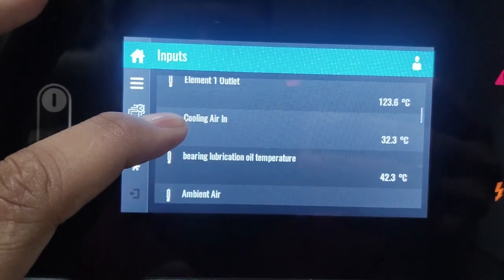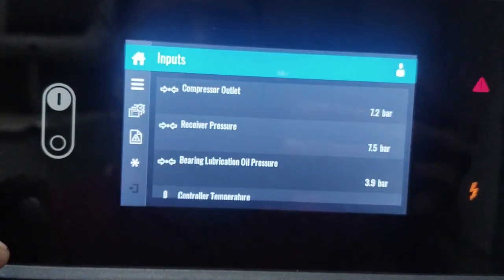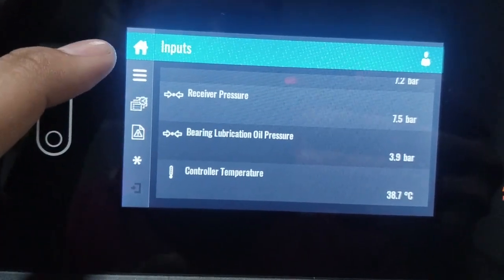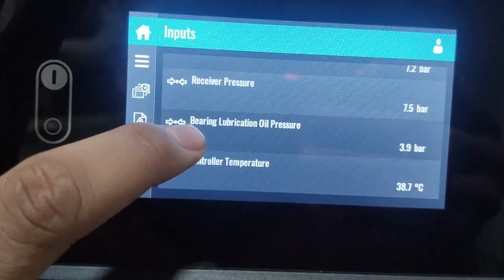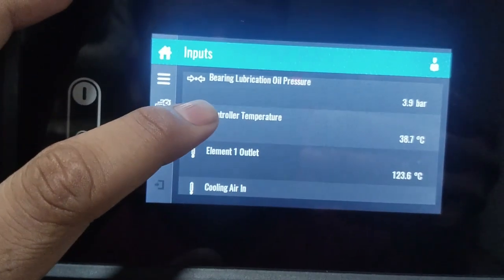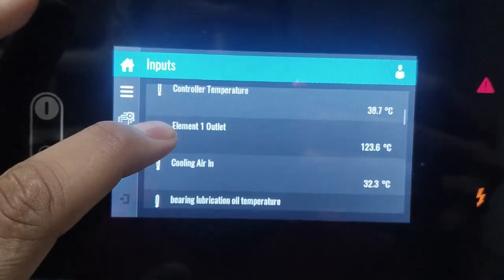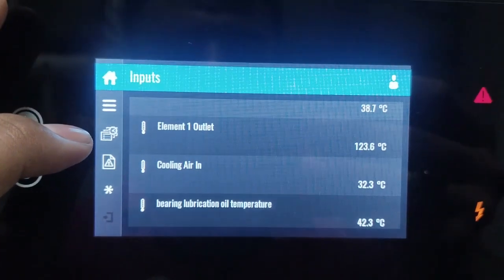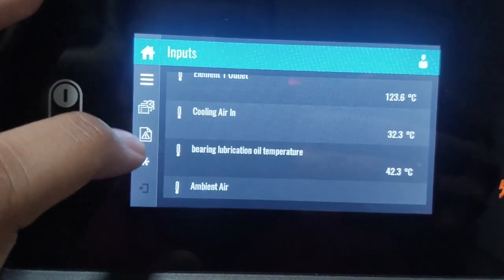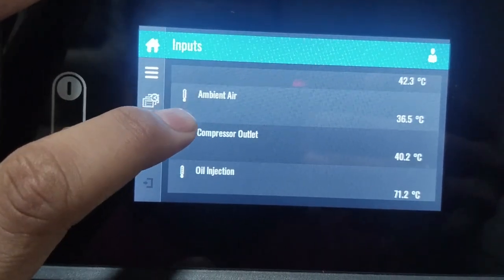Here you can see the compressor status is showing shutdown — the main reason is high temperature trip. Looking at the parameters during shutdown: compressor outlet pressure was 7.2 bar, receiver pressure was 7.5 bar, bearing lubrication oil pressure was 3.9 bar, controller temperature 38.7 degrees, element one outlet temperature 123.6 degrees, cooling air in 32.3 degrees, and bearing lubrication oil temperature 42.3 degrees, ambient air 36.5 degrees.